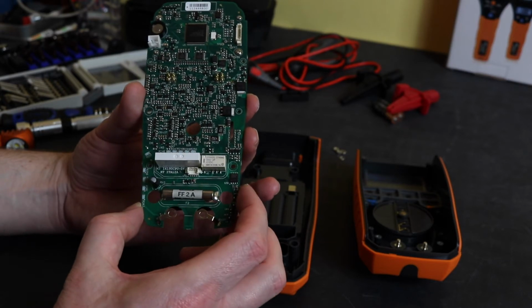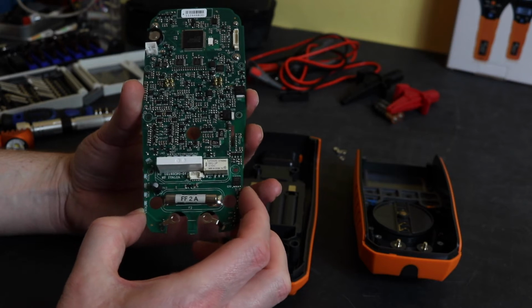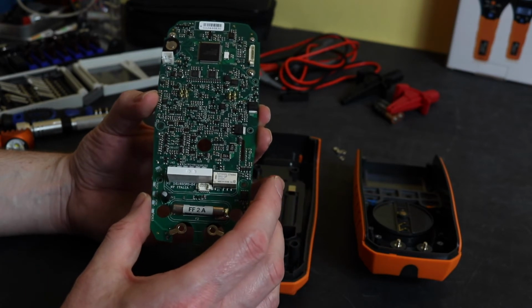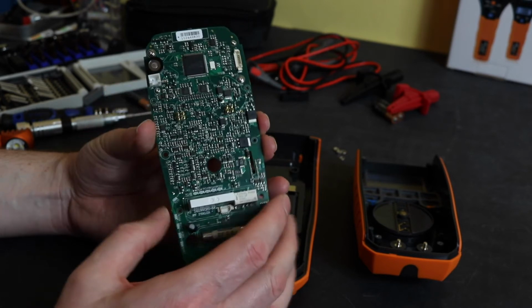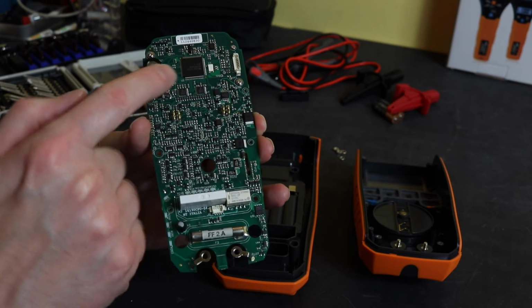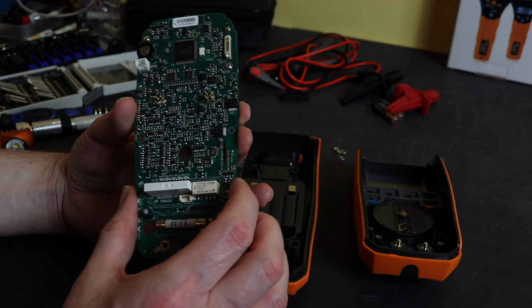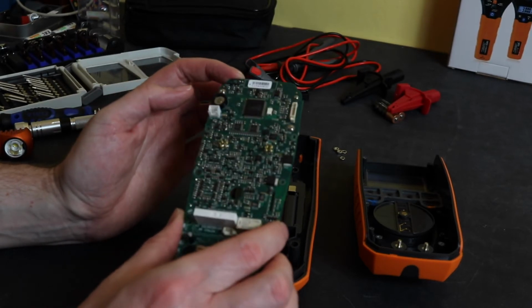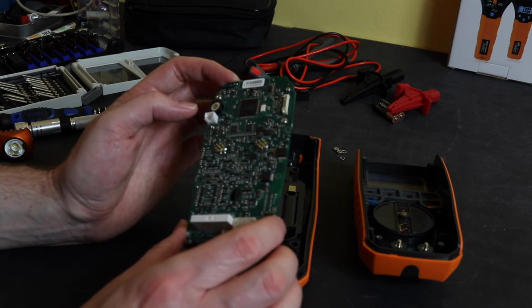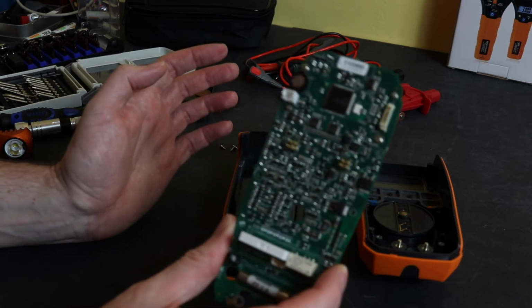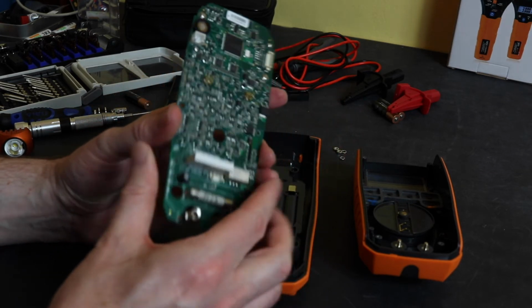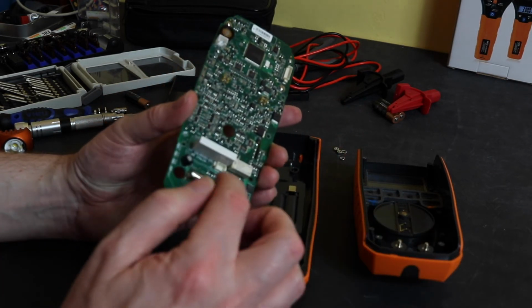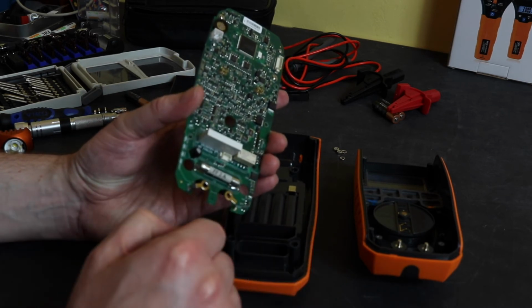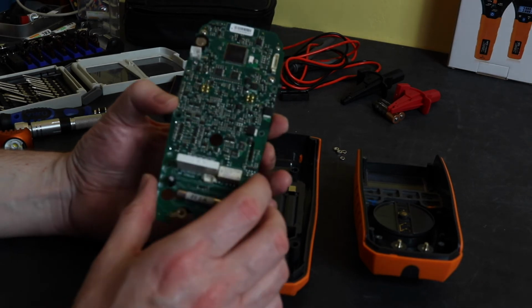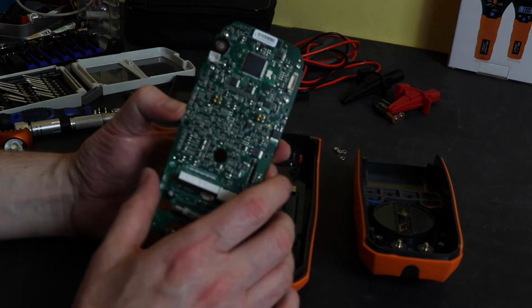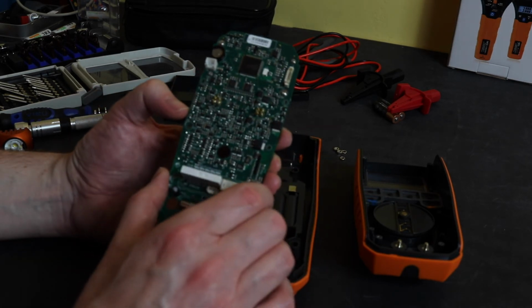The rest of the layout looks pretty clean. The board is certainly very clean. A bit congested, I guess, but it is a very, very small instrument, so that probably explains that. A couple more, yes, so there's a connector there, and a couple more connectors up there. I don't know if that's for supplying battery power or something if the PCB's out, or connecting up for calibration. You can get to this one with the instrument case closed up. A little connector there is available through the slot here. So that could be perhaps for calibration or firmware upgrades. And then these 2 are more for quality control inside the factory, I guess.